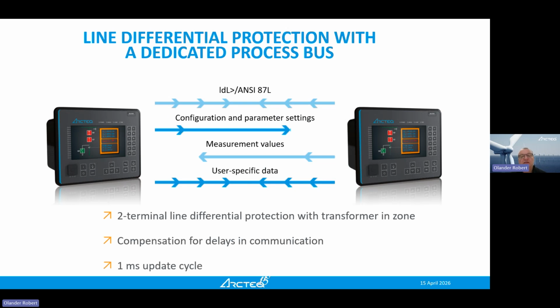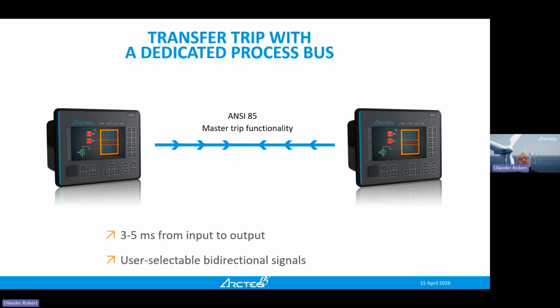There is a main device and a sub-device. So you do all configuration in the main device. It will automatically update and do the setting in the secondary device through the communication which you have between these devices. The communication typically, I would say today, is fiber. It can also be on copper, depending on what is required and what is needed. So it's a 1 millisecond update cycle, so it's very, very fast. And also you can have a master trip functionality with these devices and line differential functionality. And here again, also like said, you can have a dedicated line differential device which does nothing else, but you can also have full feeder protection here, so you can combine the functionality. It can do both feeder protection and line differential.